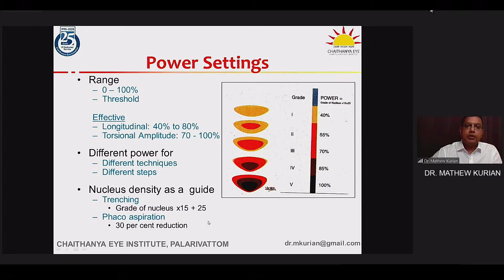You need to modify the power delivery depending on your technique and depending on the step at which you are using that particular power. A rough guide is the picture over here, where for trenching you want to use a formula which is 15 plus 25% of the nucleus grade. So for example, if it's a very soft grade 1 nucleus, you're using 15 plus 25, that's 40% power. A much harder cataract would require a much higher level of power.